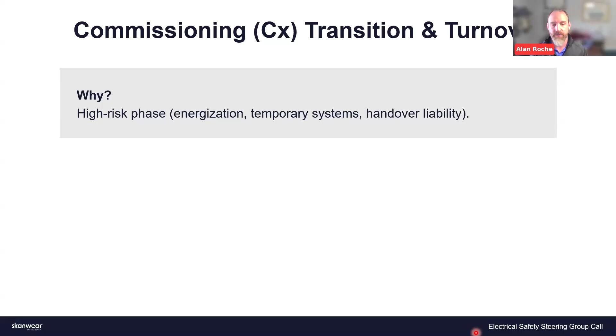Talking about the first time energizations, it's the first time the equipment's going to operate at full power. So it's when those electrical faults can become arc flash hazards. We talked at the conference about this - had everybody raise their hand, how many people have seen arc flashes upon initial energization, and most of the room's hands were still up when I asked if people knew of 5 incidents over the last year.